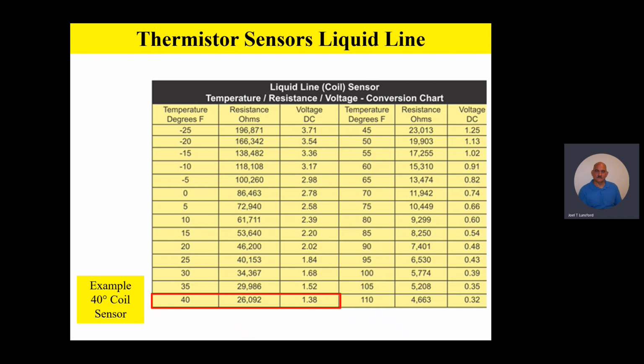Well, you'll notice on these charts, they all work the same. As long as you've got the temperature, you're going to have a resistance column and you're going to have a voltage column. And so in this example, let's say we have a coil temperature of 40 degrees and we actually clamp on with our electronic temperature probe, and my actual coil temperature in this example is 40 degrees. Well, if I unplug that coil sensor from the board and read the ohms, it should be about 26,000 ohms and some change. If I plug that sensor back onto the board and dig in with my needlepoint meter leads back behind the harness, it should read 1.38 volt DC with the sensor plugged back on.